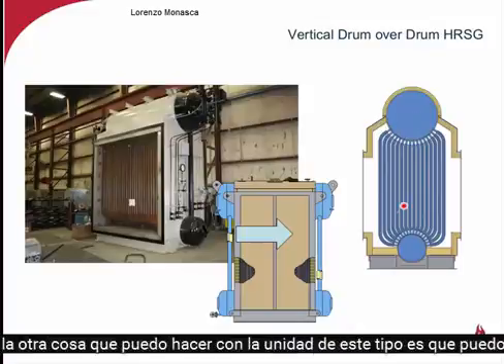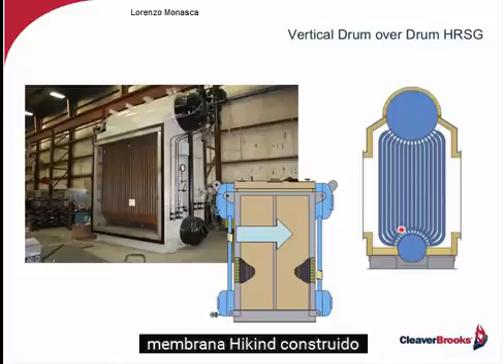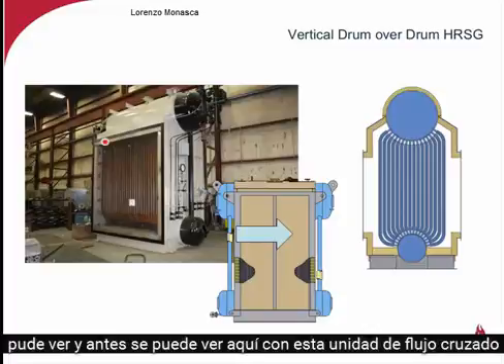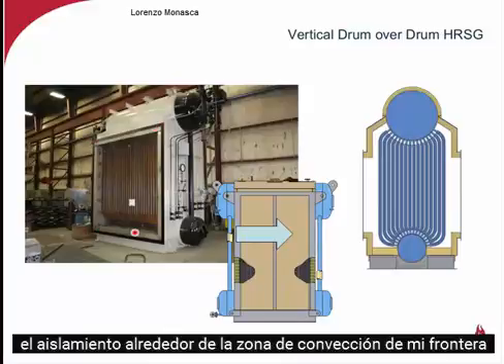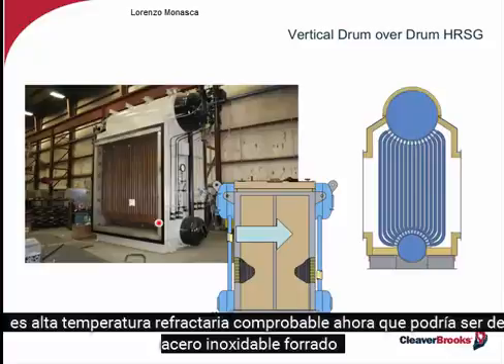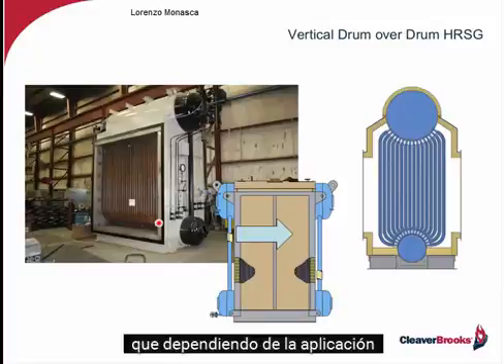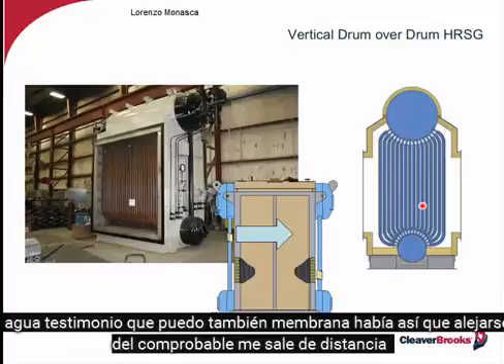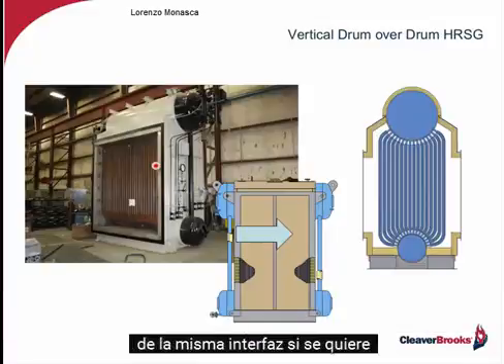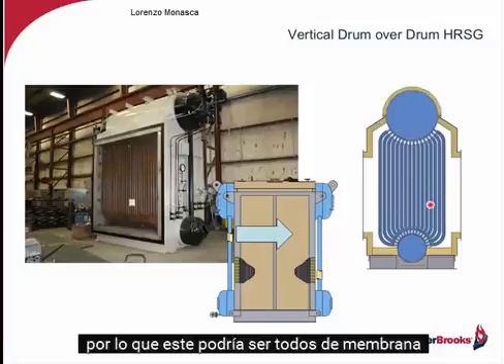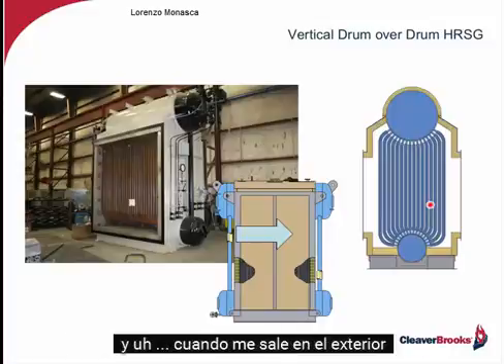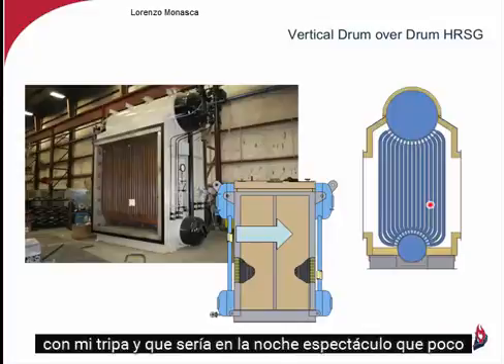The other thing that I can do with a unit such as this is I can membrane construct it. On this unit that you see here, well, you can see right here, with this cross-flow unit, the insulation around the convective area of my boiler is high-temperature castable or refractory. Now, that could be stainless steel lined as well, depending upon the application. With this boiler, I can also membrane it. So I get away from the castable. I get away from this inner casing, if you will. Another maintenance headache. So this could all be membraned. And I would just then have to insulate and lag it on the outside with my casing, and that would be it. And I'll show you that in a little bit.